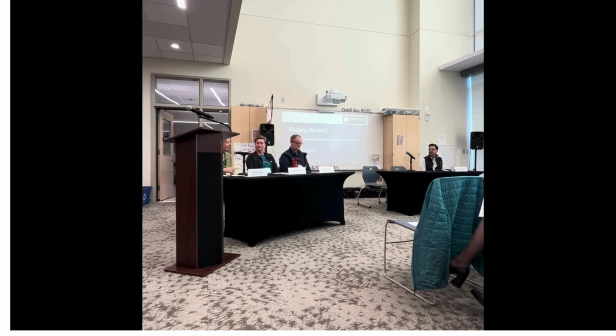Go to Kate. Speaking of leaks, during the first fall when we occupied the building, the construction team was working to demolish the old elementary school, which was side by side with the new building. They were near the end of the demolition process and going after a transite pipe that had been left towards the end because of contamination. A digger was working to get it, and in that process managed to snag a geothermal loop and tore it open. We lost a lot of geothermal fluid out of the system with that.